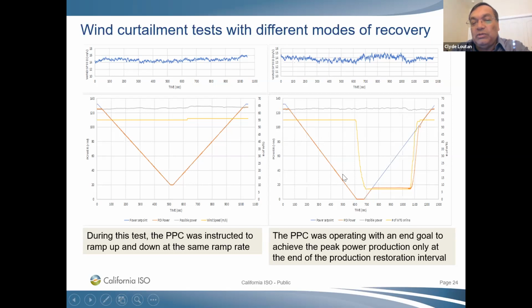On the right, the control is a little different. We were able to ramp this unit at a constant power factor from roughly 130 megawatts to 0. But then coming back up, you can do a few things. If you look at the right, this is the number of individual turbines that were committed. But in this mode, even though you have the turbines committed there, you do not recover. So this mode of operation is to recover at a certain point in time.